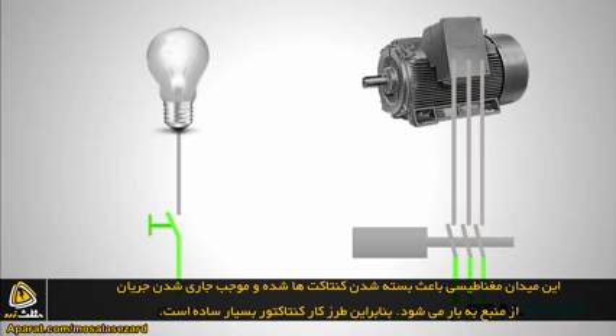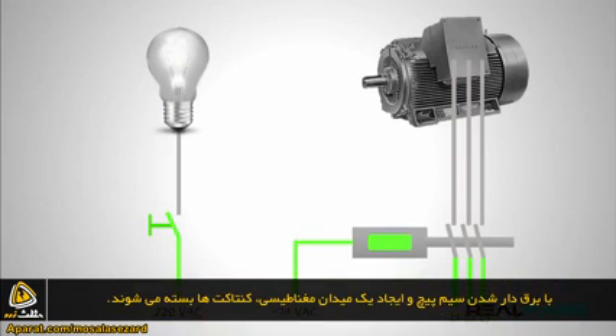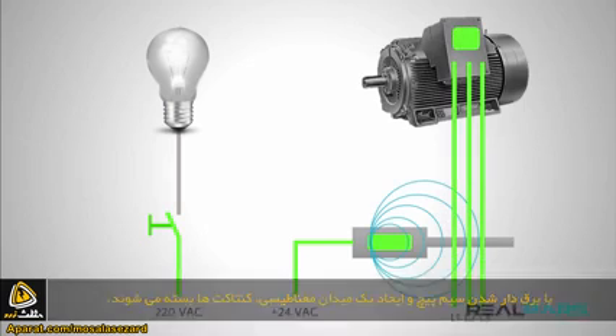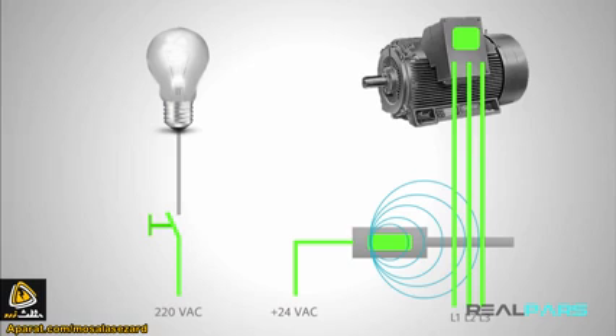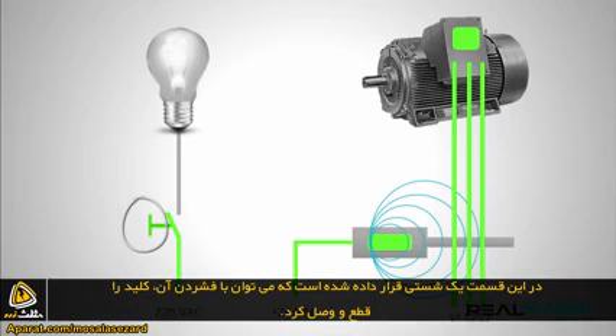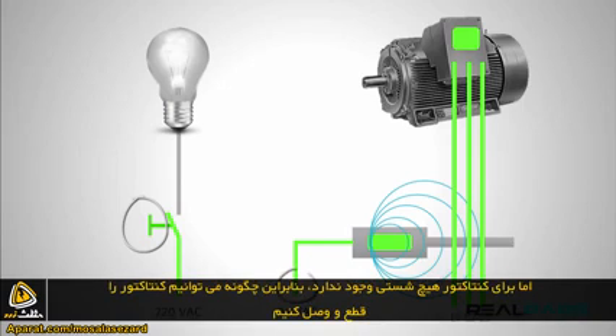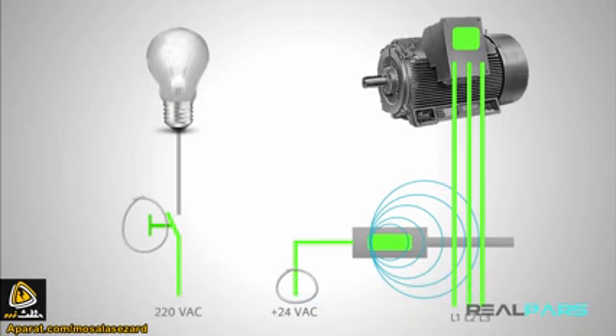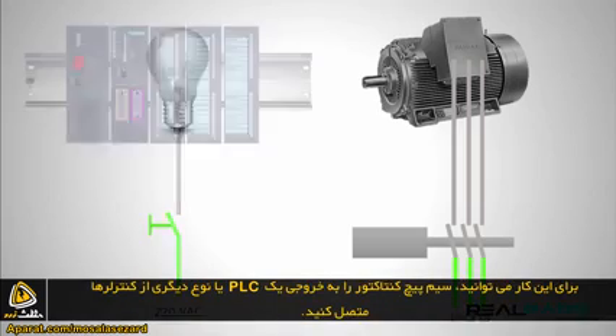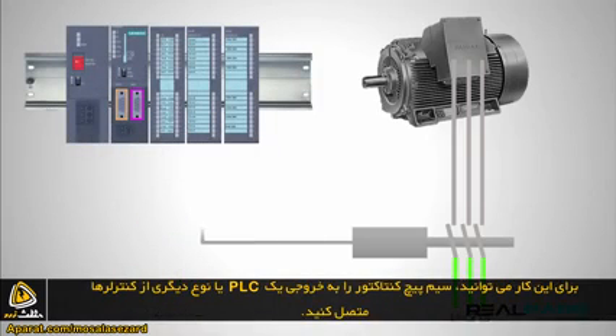So the contactor functionality is very simple. When the coil is energized and an electromagnetic field is created, the contacts will be closed. We've added a button here that you can push to close and open the switch. But we have no button for the contactor. So how could you demand the contactor to close or open? You can do this by connecting the contactor's coil to a PLC output or any other type of controller.